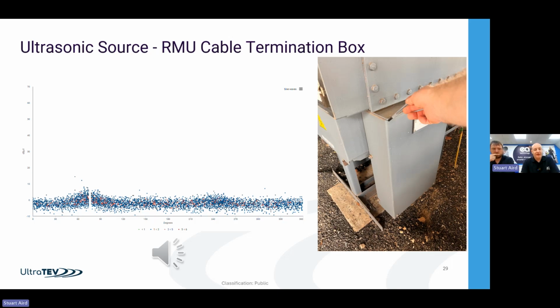As you can see, it's quite quiet, and you've got to make sure you've got your microphone in exactly the right area. So it does take a bit of care, making sure you're listening right round all those gaps in the cable termination boxes. Obviously, if we can install the Ultrabolt into these cable termination boxes, that would eliminate the chance of missing something. I imagine if we open this up it'll be considerably louder inside, and the Ultrabolt will give a much stronger signal, but here we're picking up through this tiny little hole in the top right, basically the fold of the steel in the corner there. So that would be a big improvement, to use the Ultrabolts on these ones.